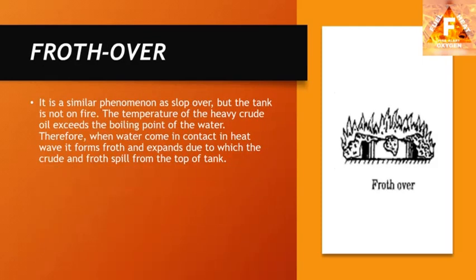Then we have froth over. Froth over is similar in scenario to slop over, but here the tank is not on fire. It is an overflow of a non-burning flammable liquid from a tank or container due to thermal expansion of the liquid, or violent boiling on top and within the upper layer of the liquid due to the presence of small quantities of water.